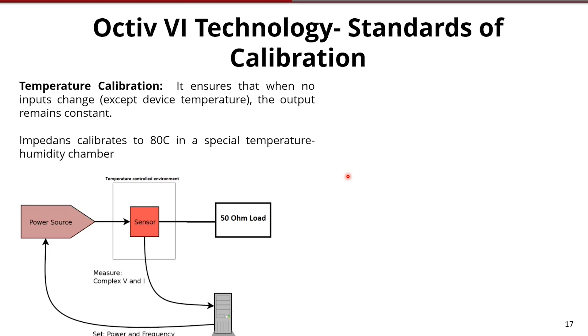One thing is you have to calibrate by temperature, because you don't want the sensor to give different measurements depending on the room temperature or the temperature of the cable if you're running high power or so on. It needs to be able to work at different temperatures, so we calibrate our sensors from room temperature to 80C in a special temperature humidity chamber. So all our sensors go through that—that's something you need to do with a VI probe.